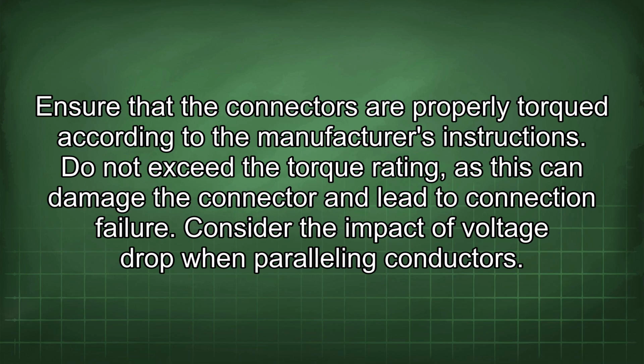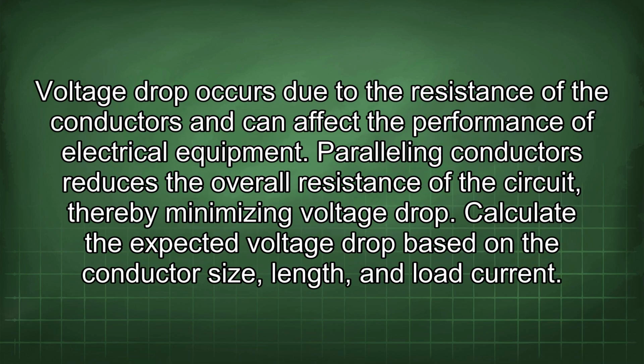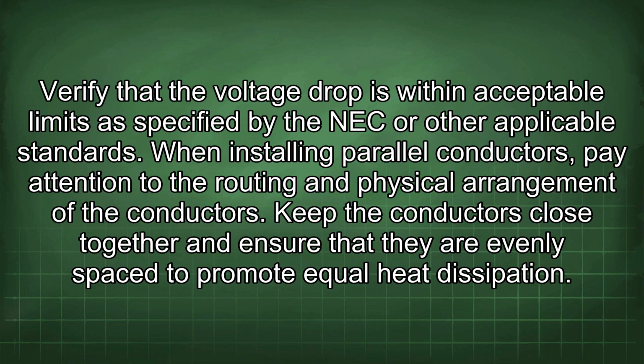Consider the impact of voltage drop when paralleling conductors. Voltage drop occurs due to the resistance of the conductors and can affect the performance of electrical equipment. Paralleling conductors reduces the overall resistance of the circuit, thereby minimizing voltage drop. Calculate the expected voltage drop based on the conductor size, length, and load current. Verify that the voltage drop is within acceptable limits as specified by the NEC or other applicable standards.